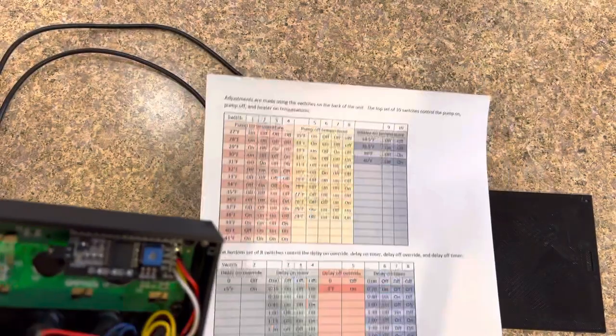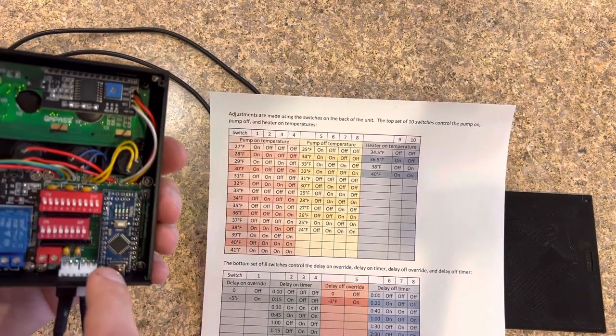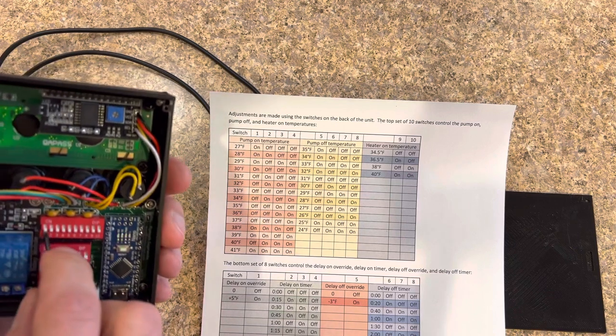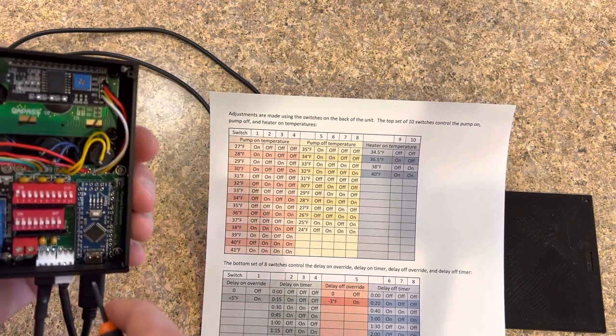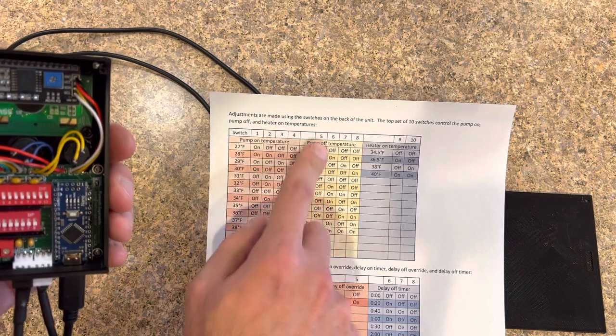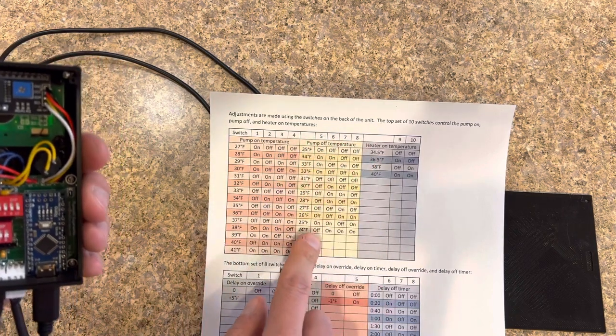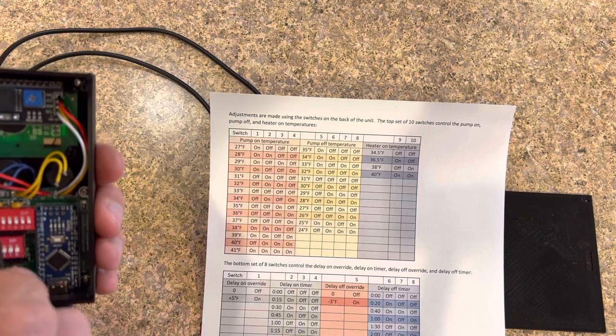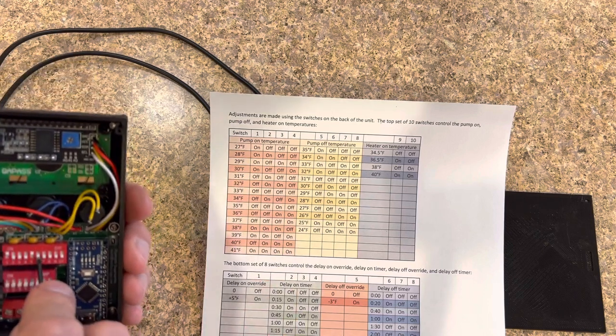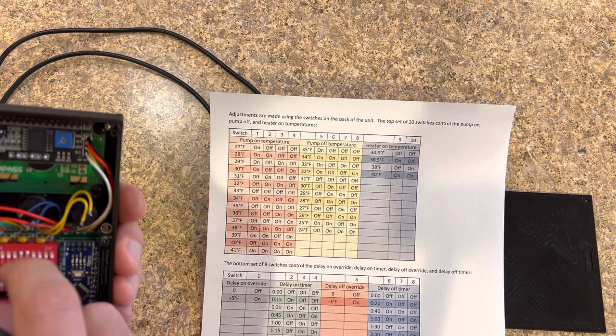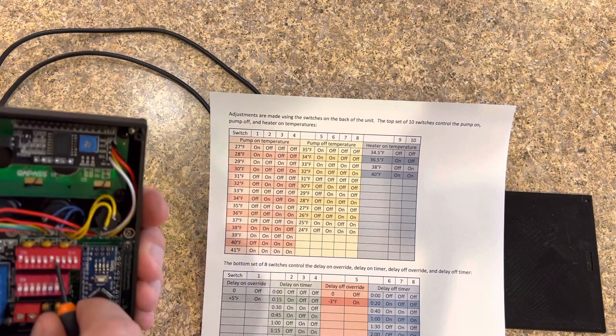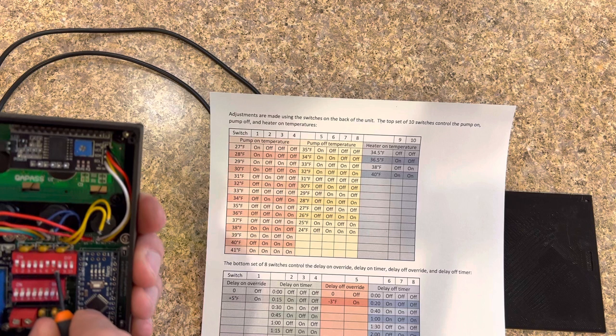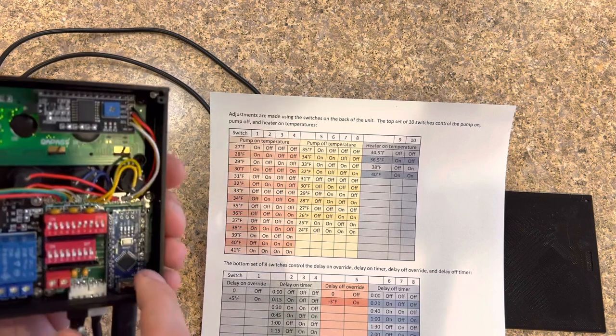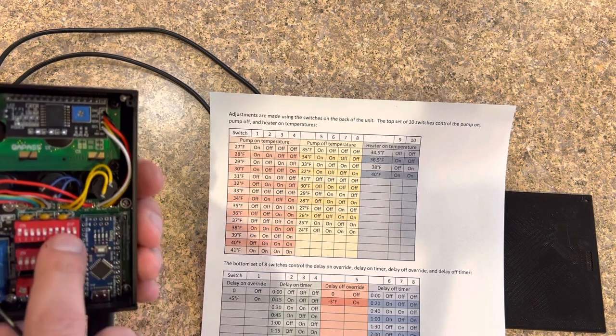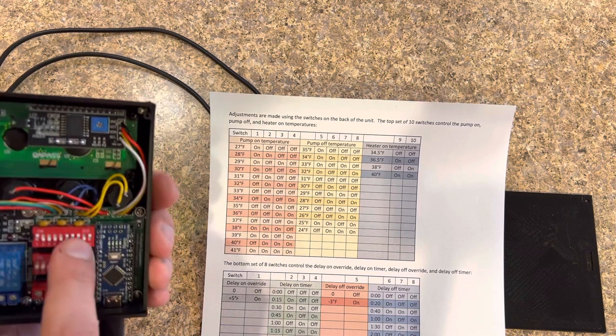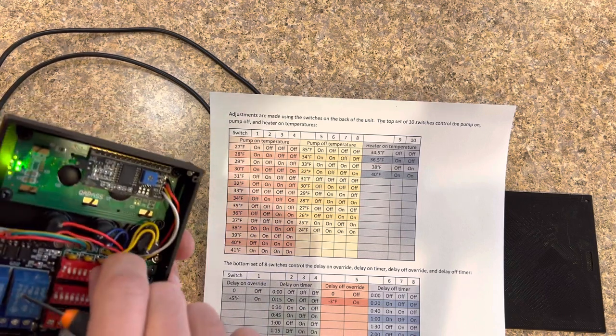But if we look at this chart here, if I wanted to change it to turn on at 27 degrees, this first jumper goes up. And then if we wanted it to turn off at, say, 24 degrees, you can see jumpers 5, 6, 7, and 8. We want off, on, on. So jumper 5, oops, sorry, off, on. And then we can turn the heater temperature on to say 40 degrees. So these last two jumpers will flip up here.